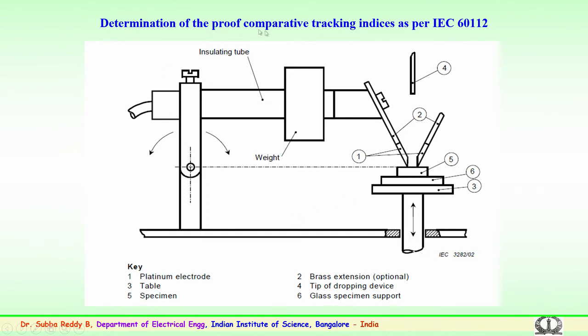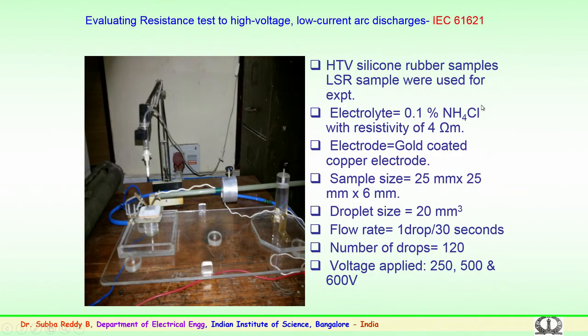So, the entire arrangement has to be fabricated for studying the comparative tracking index. This is with reference to IEC 60112 standard. So, we have tried to fabricate a similar arrangement. You can see here 2 electrodes, especially gold coated electrodes, have been used at a known distance, and the droplets of the contaminants are supposed to be dropped at regular intervals.